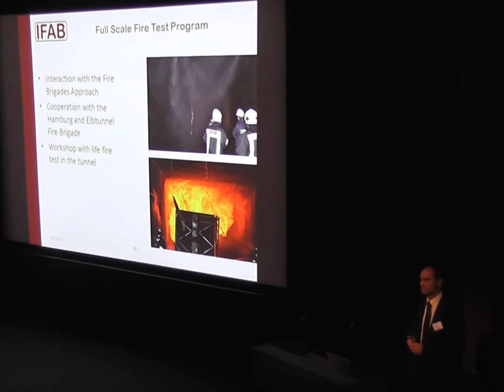Coming a little bit to curves and to the interesting things now. As I said, we did Class B fires. I just picked now one fire test, and just want to go with you a little bit into the curves. There will be much more publications in the near future. At the moment we're still working a lot with the data and had not really the time to work on the publications, but they will come in the near future. We have, as I said, Class B fires up to 100 megawatts, diesel fires, and they were not covered. That's also quite important to know, because there's written they were extinguished.